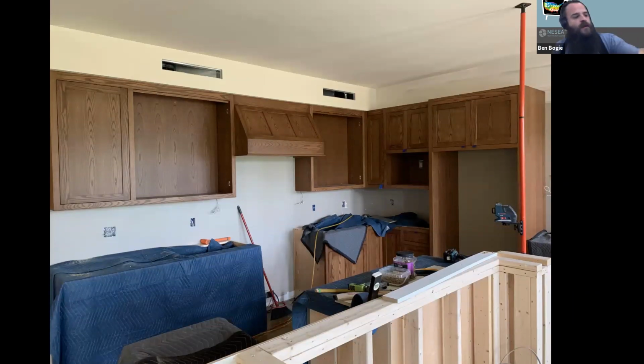Oh, one more thing - this is a dirty shot, but I had it on my phone. You can see the makeup air coming in right there, behind where the range will sit. Something Ross touched on before is making sure we have a properly sized hood - I want it to come all the way out to the front of the cooking surface, and extend past on the sides as much as possible. Commercial kitchen codes usually require extending about 18 inches to 2 feet out in any direction from the cooking surface to ensure capture. That's a hard sell in residential, but this is about as best as we can get.